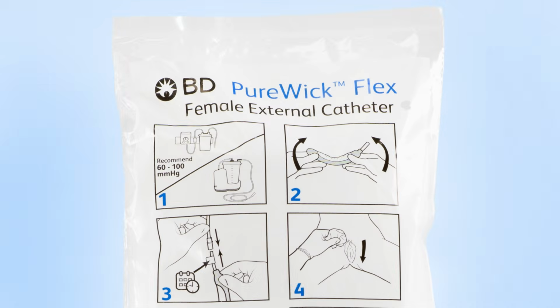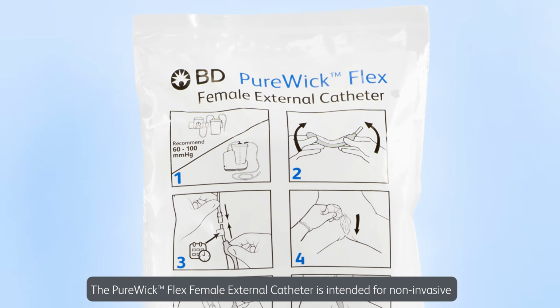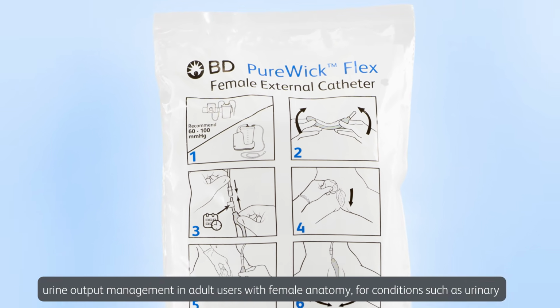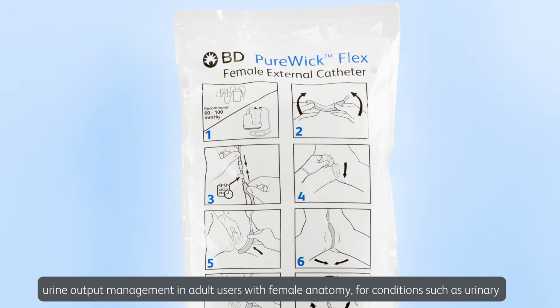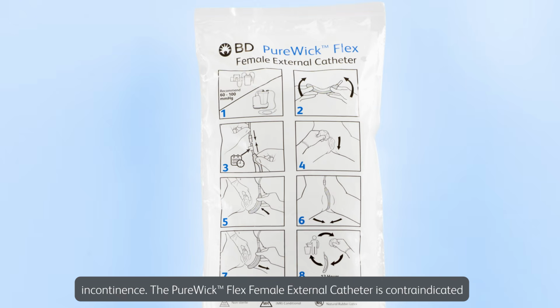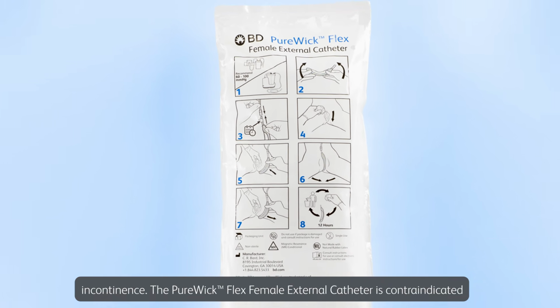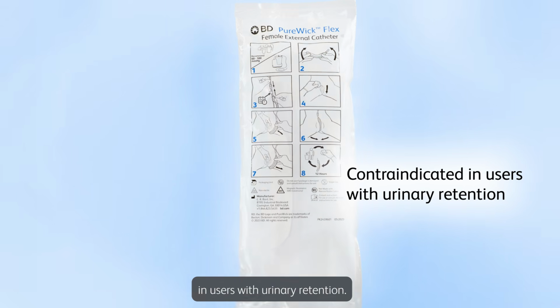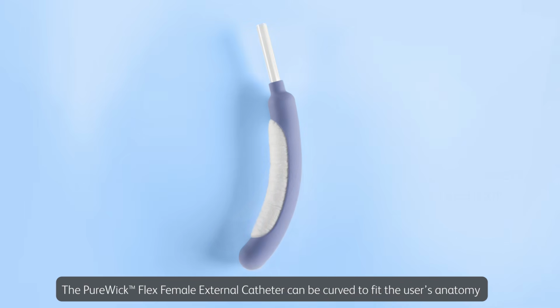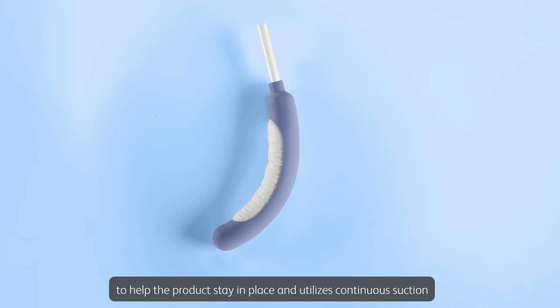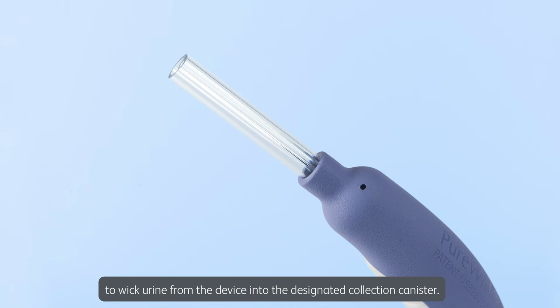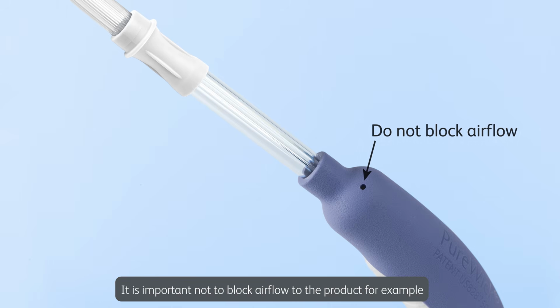Introduction. The PureWick Flex female external catheter is intended for non-invasive urine output management in adult users with female anatomy for conditions such as urinary incontinence. It is contraindicated in users with urinary retention. It can be curved to fit the user's anatomy to help the product stay in place, and utilizes continuous suction to wick urine from the device into the designated collection canister. It is important not to block airflow to the product, for example, block the vent hole using barrier creams or bedpans with the device.